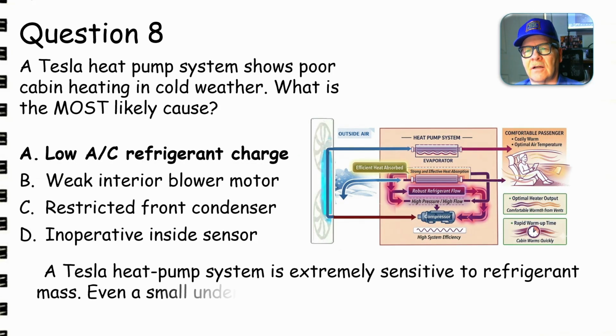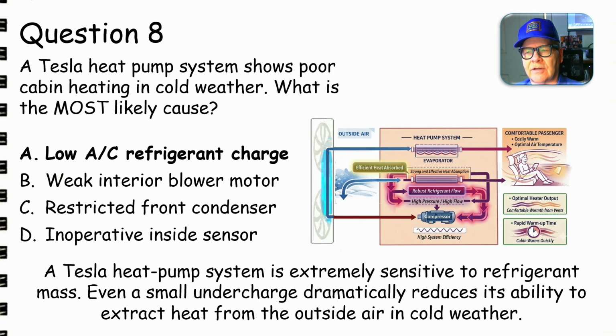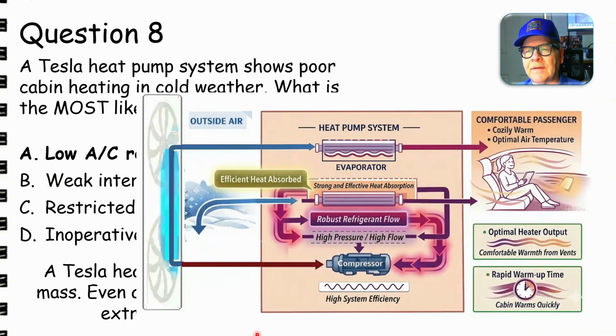Believe it or not, low AC refrigerant charge is the answer to this. It's sensitive to refrigerant mass. Even a little undercharge reduces its ability to extract heat from outside air in cold weather, because it needs that refrigerant going through there, the right amount, to be able to draw heat from out here and pump it into the cabin. And there's a zoom in on that one there.